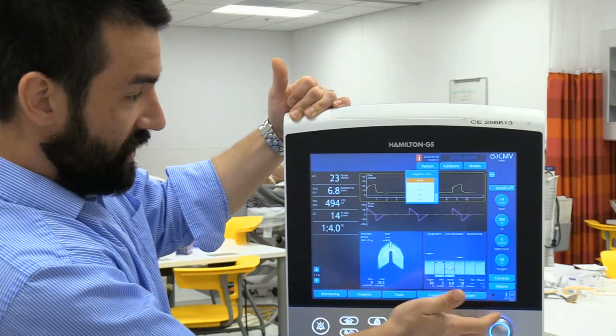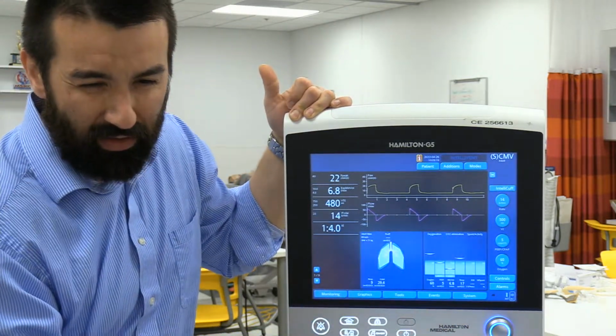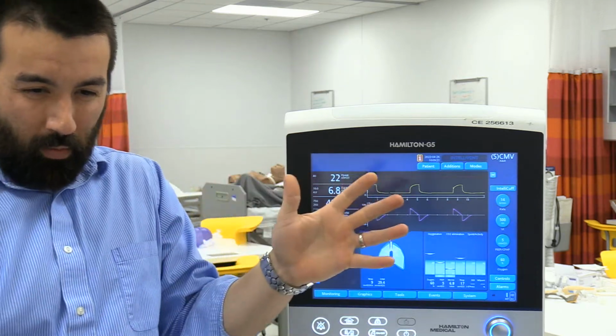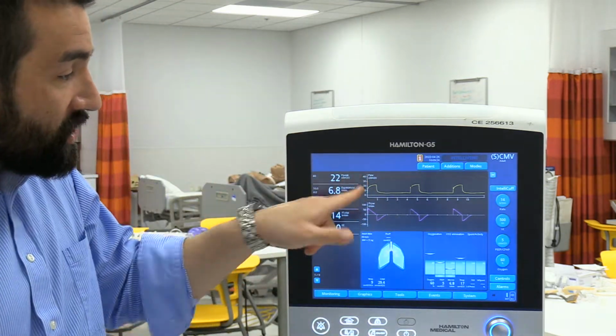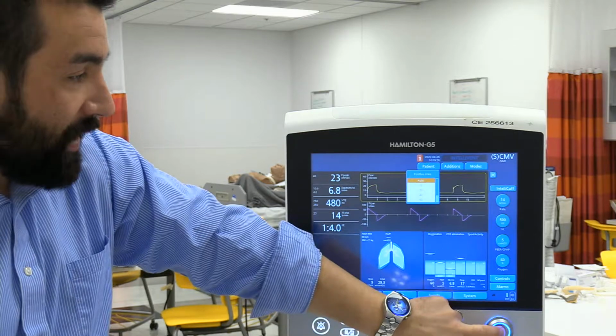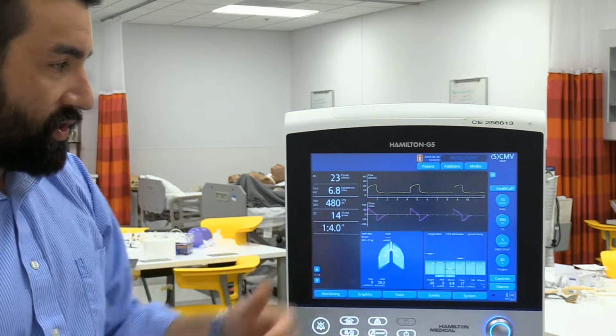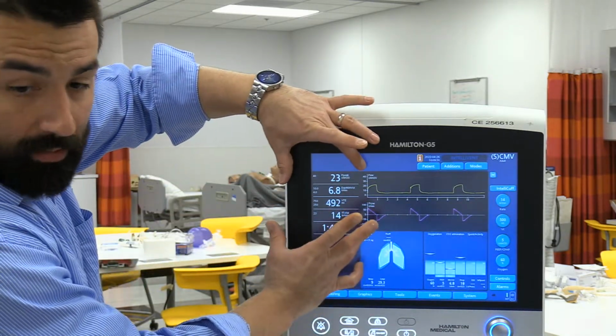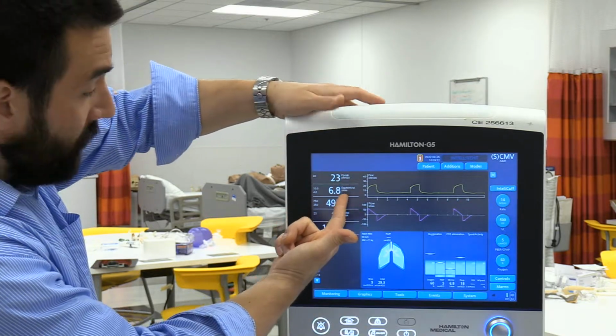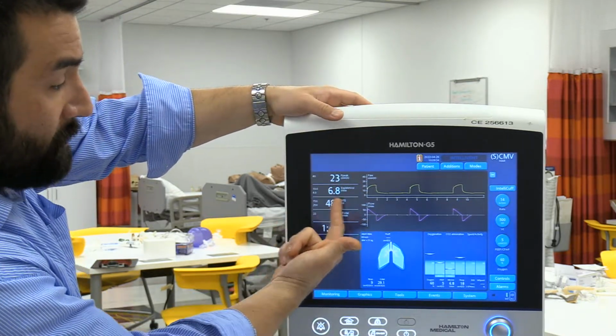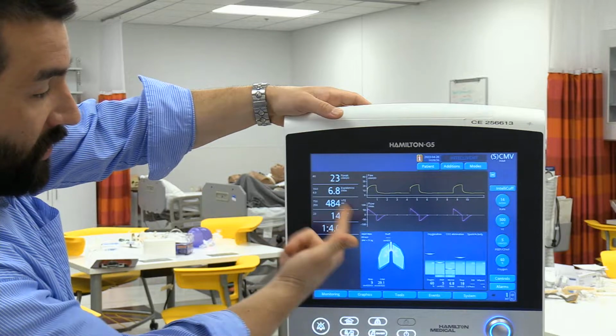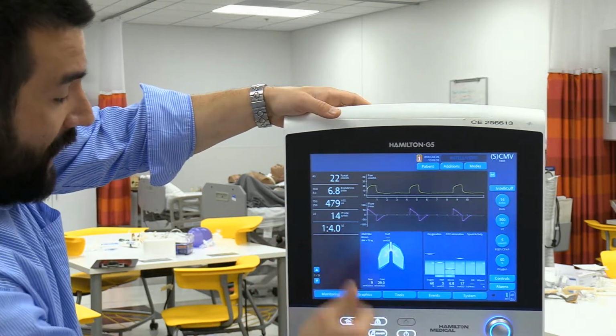So it's fine on the G5 doing auto. It's a little bit bigger screen. On the C3, I'll hit it, it defaults to like 21 seconds, and everything's tiny. You can change the time scale here for how many seconds it's looking at. Auto is usually pretty good on the G5. Real-time measurements are taking place over here, so you can see peak airway pressure, minute ventilation, my VTE or exhaled tidal volume, current respiratory rate is F total, and your I to E.